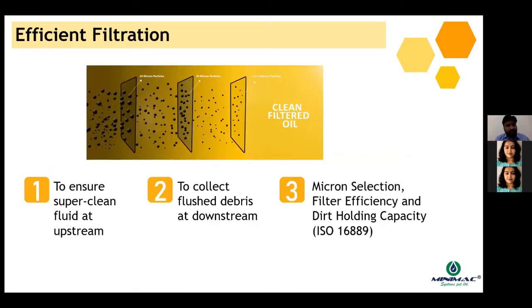Efficient filtration. So we all know that filtration would be required during the scope of flushing, because when you are flushing, you are actually capturing a lot of debris from the piping network. And when the fluid is returning on the downstream of your flushing loop, there would be a huge amount of debris in it. Hence, it's very important to understand how to have filtration, or how to capture this debris at the right time. Because if you do not clean or filter the debris out, the same would keep on rotating in the pipeline and flushing would never conclude.